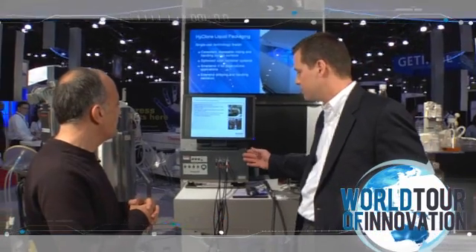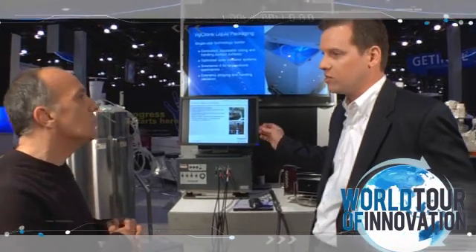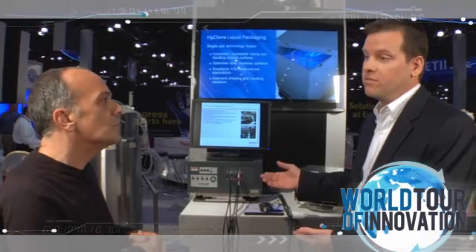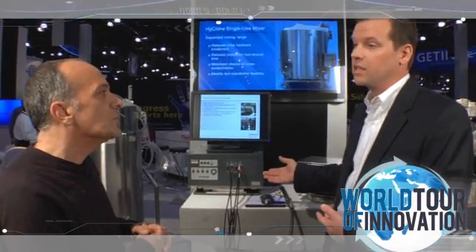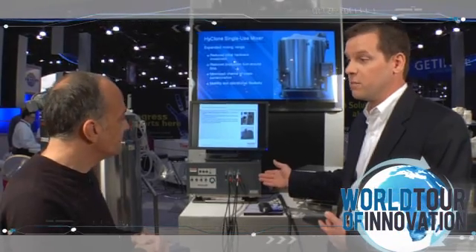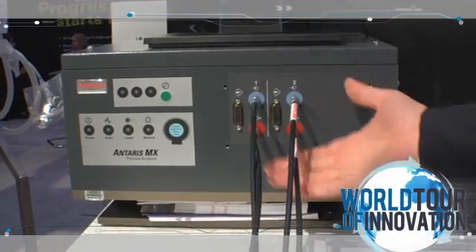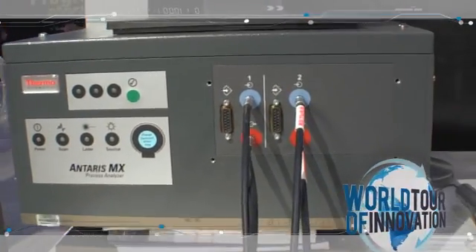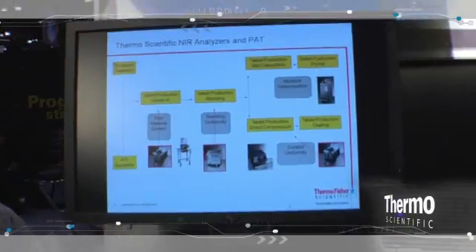The Antaris MX is based on our laboratory platform. If we're developing a model or a method for our pharmaceutical customers in the lab, they have the ability to directly transfer that method onto the Antaris MX using fiber optics. This system has up to two or four-channel fiber optic capabilities, giving customers the opportunity to monitor multiple processes simultaneously — one of the real features is its true simultaneous multiplexing using fiber optics.